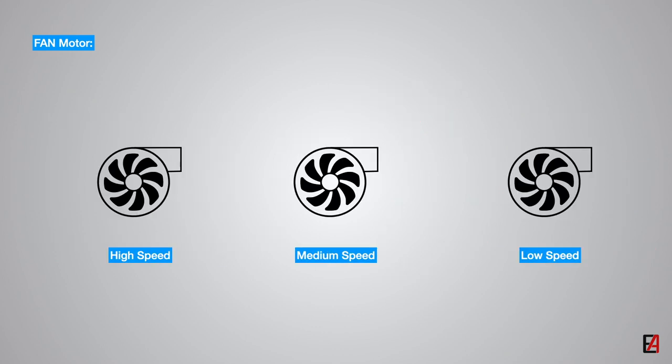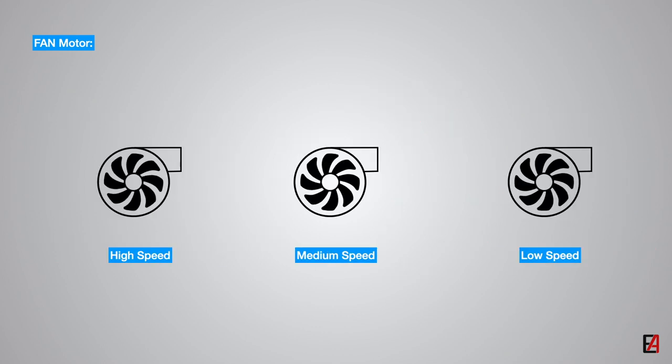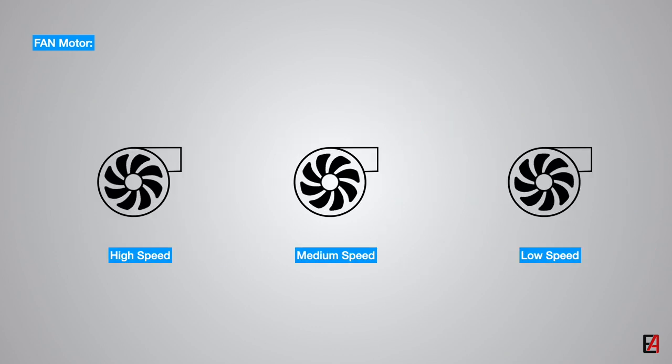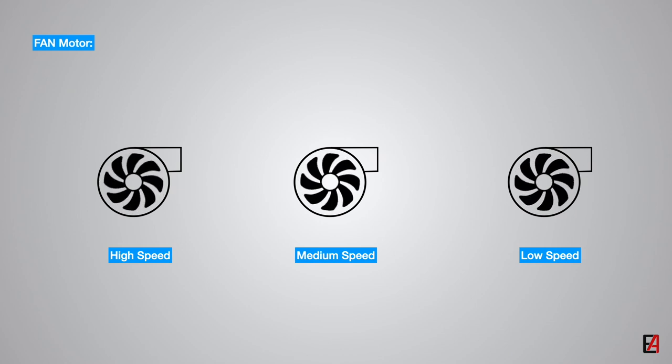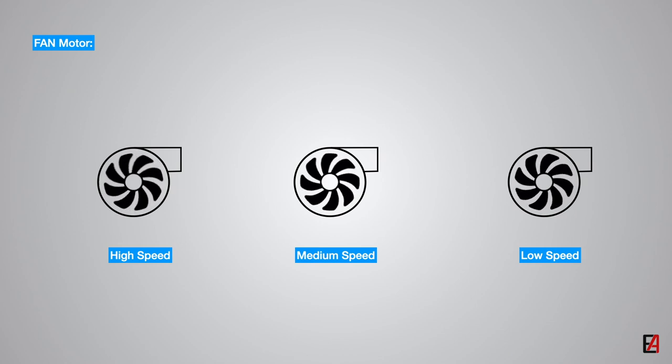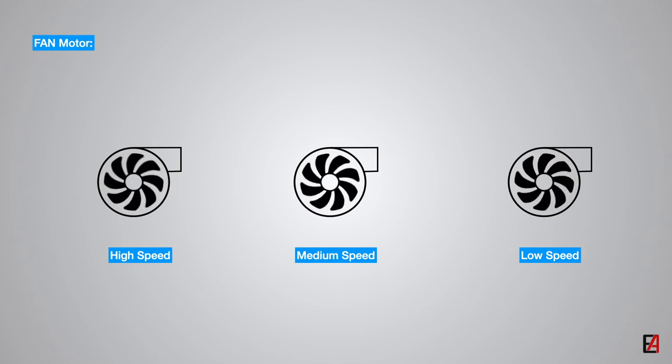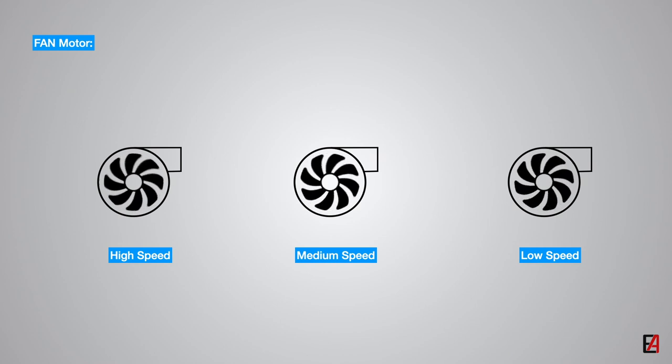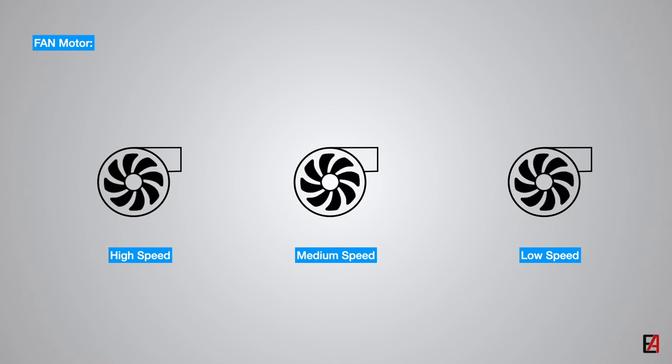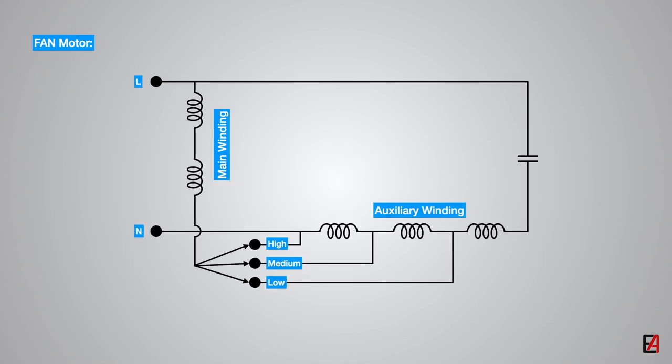Typically, the fan coil unit motor is operated in three speeds: high, medium, and low. The three-speed operation of the motor is achieved by having three-speed tappings on the auxiliary winding as shown here. The tapping allows to vary the voltage applied to the main and the auxiliary windings.